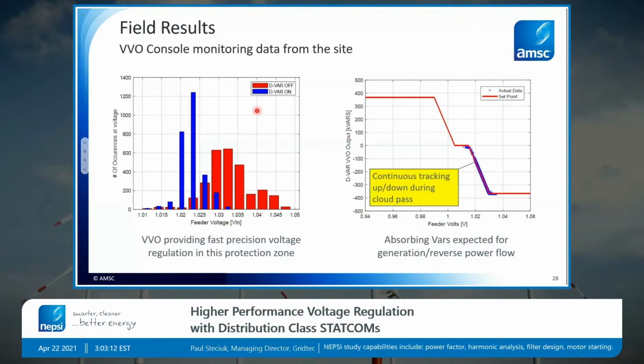This is also on a couple of days where the loading was a little more significant, so the high voltages when the D-VAR is off aren't as high. And the utility didn't want us doing this testing on the worst case days so that we could not create voltage violations. So basically the red histogram is with the VVO turned off, and we see a wide spread of voltage as well as significant high voltage. And when the VVO is turned on, we see a nice tight histogram. And even as the solar increases on that circuit and the load decreases, so the red would be wider, that blue histogram stays nice and tight even at higher reverse power flow levels. So it's a good way to see how precisely the VVO is able to regulate voltage as the primary voltage regulator on the branch circuit where that solar plant was integrated.